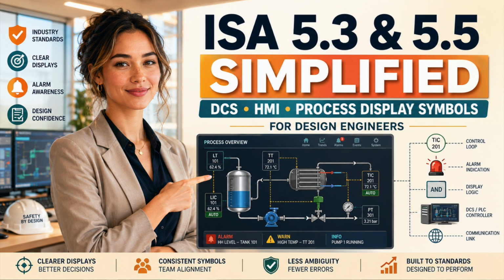That failure begins when you treat the process display as decoration. A process display is not artwork, and it is not a digital copy of a piping and instrumentation diagram. It is an operating decision surface. It must help the operator perceive what is happening, understand why it is happening, decide what must be done, and act before the process moves beyond safe or recoverable limits. The operator should spend mental capacity understanding the process, not decoding your display. That single principle should govern symbols, colors, equipment states, alarms, navigation, control modes, data quality, communication failures, and fallback arrangements.